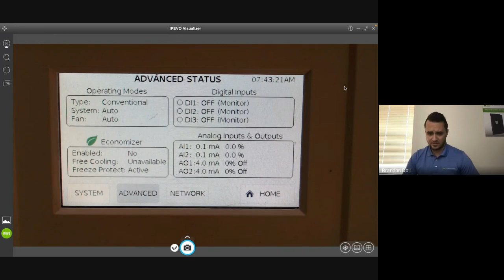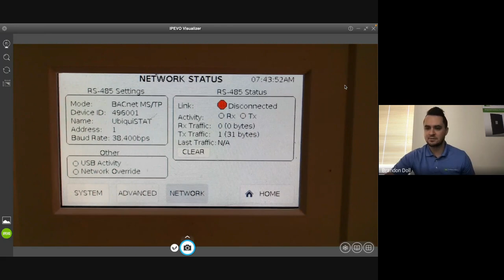You're going to be able to see your digital inputs and your analog inputs and outputs. And if it was hooked up to live equipment, you'd be able to see your milliamperage fluctuating and the percent of it. Your network page: I don't have this hooked up to live equipment, but if I did, you would see a green circle connected, and you'd be able to see the activity right there. You're seeing we're in the BACnet MSTP mode, your device ID, and the baud rate you're running on. So pretty powerful, just to let you know that, hey, I did hook this up correctly, it's communicating. This stat is wired right.